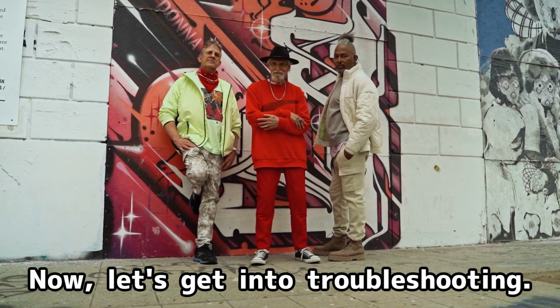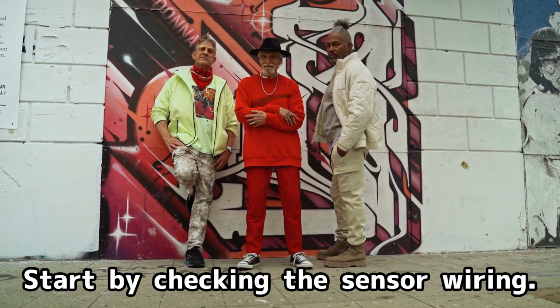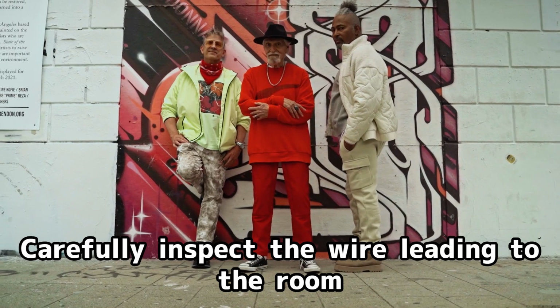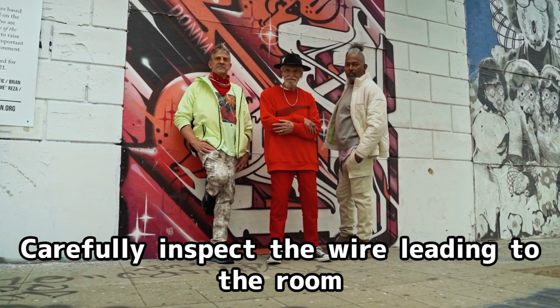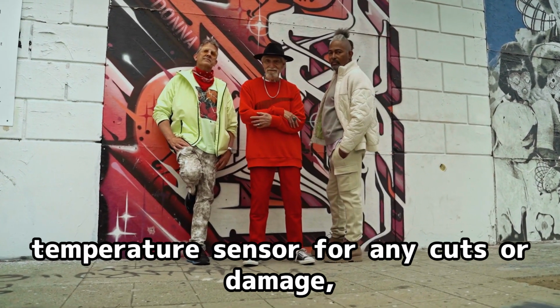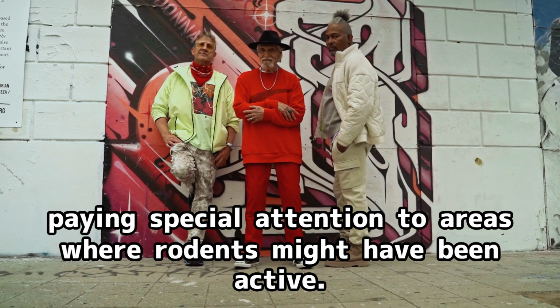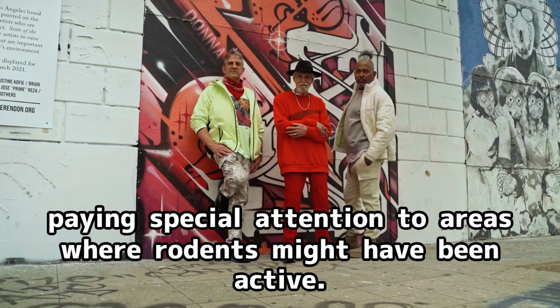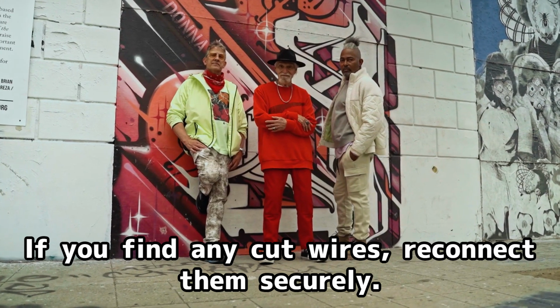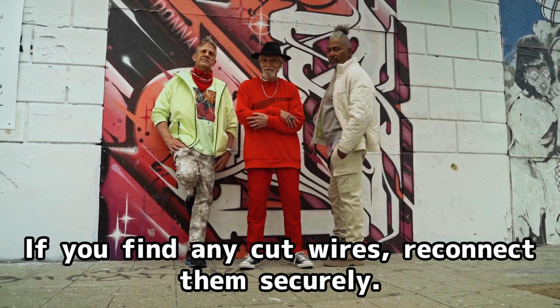Now, let's get into troubleshooting. Start by checking the sensor wiring. Carefully inspect the wire leading to the room temperature sensor for any cuts or damage, paying special attention to areas where rodents might have been active. If you find any cut wires, reconnect them securely.